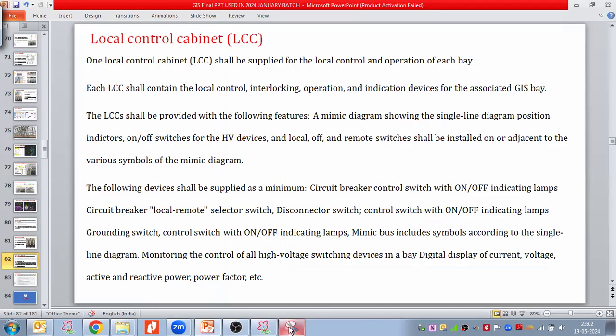So we take the LCC, in which we develop the same SLD, and the GIS supplier will develop it on the local control cabinet, on the outside upper side of the door. Each and every equipment's operations and indications are to be provided, so that by looking at the LCC you can see which equipment is in closed or open condition, and their operations can also be done from the LCC.